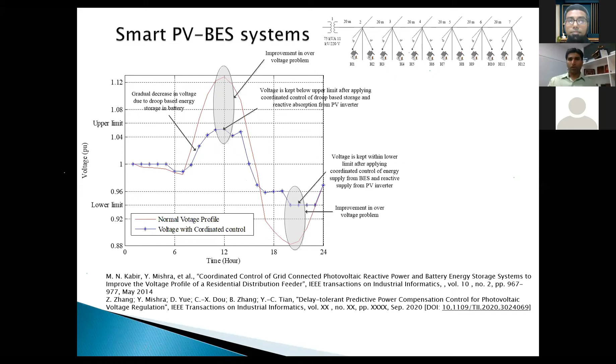In the evening, you supply from the battery and also use reactive power to improve the voltage, which solves the reactive power problem and improves the system. More recently, we realized the battery controllers and inverter controllers need to communicate with each other. We wrote a paper about what happens when there's a delay in communication from the central substation controller to individual controllers, finding that predictive power compensation control works better with such delay from the central controller to the slave controllers.